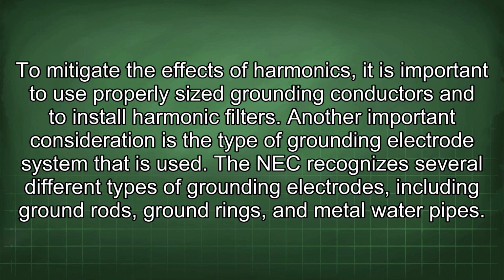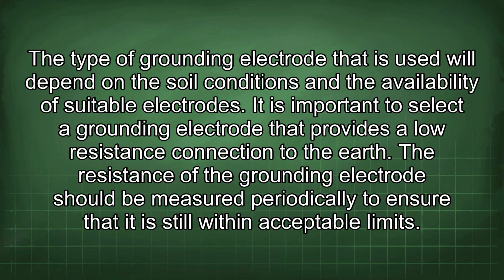Another important consideration is the type of grounding electrode system that is used. The NEC recognizes several different types of grounding electrodes, including ground rods, ground rings, and metal water pipes. The type of grounding electrode that is used will depend on the soil conditions and the availability of suitable electrodes. It is important to select a grounding electrode that provides a low resistance connection to the earth.